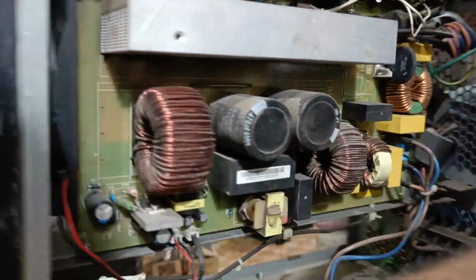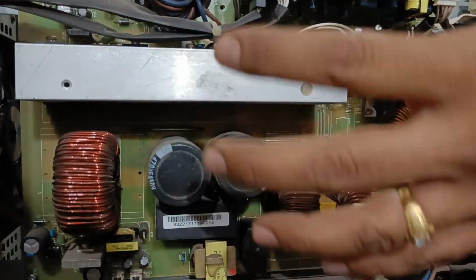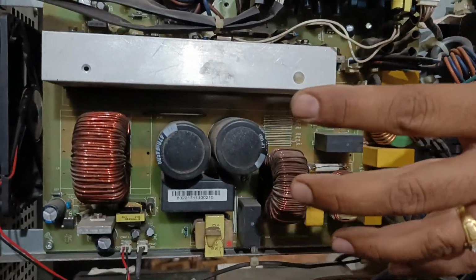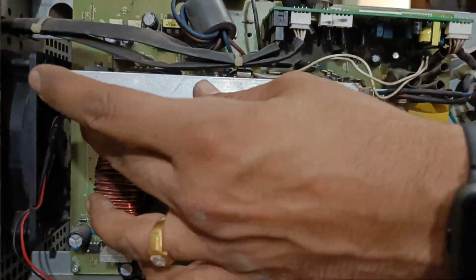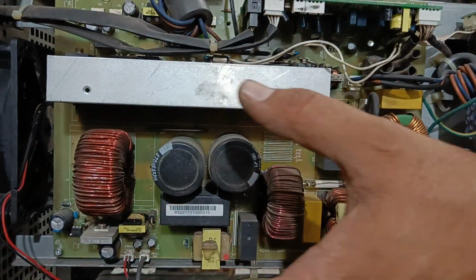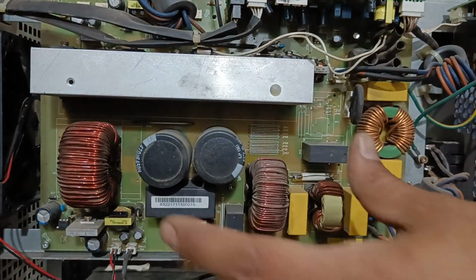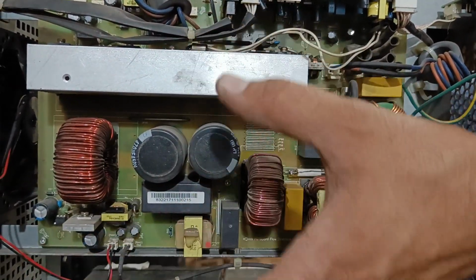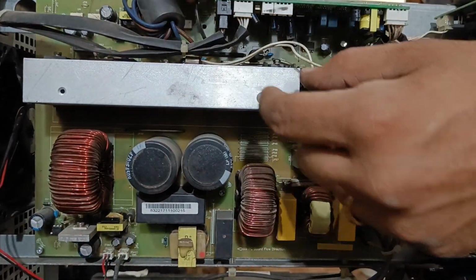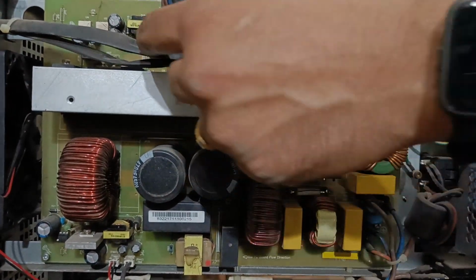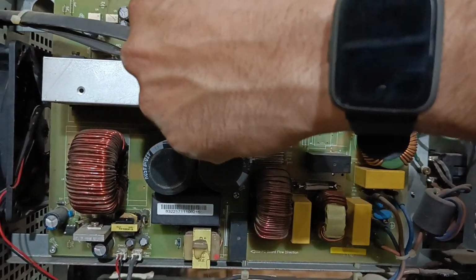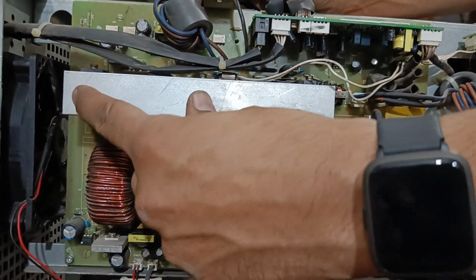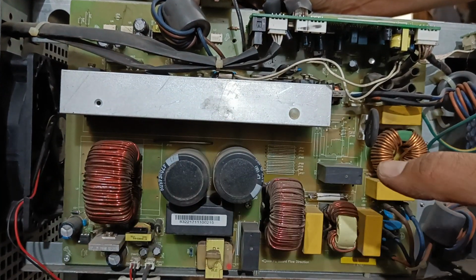On the right side of the UPS, this is a combination of two parts. This card has the inverter section and the input PFC section. The inverter section, as you know, inverts the DC voltage into AC voltage. We put the DC voltage plus minus 350 volt here, I turn on the inverter, it inverts it, and we get the output voltage.